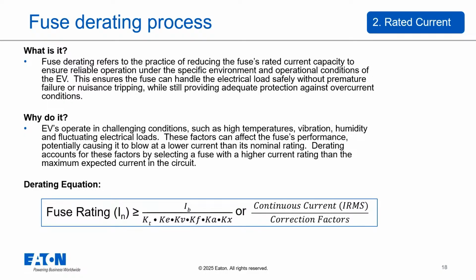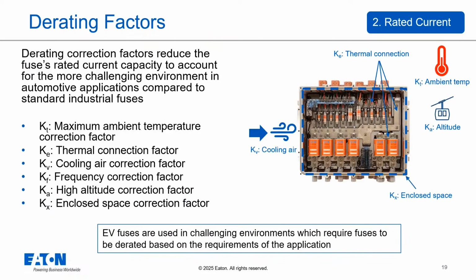K sub T accounts for the maximum ambient temperature the fuse will experience. K sub E relates to thermal connection, influenced by things like wire size. K sub V, for cooling air, accounts for whether there's active airflow or not. K sub F, a frequency correction factor relevant for AC circuits, less critically for purely DC EV systems. K sub A corrects for high altitude operation. K sub X applies if the fuse is enclosed in a confined space. Because EV fuses are in these demanding environments, they must be derated based on the specific application requirements.